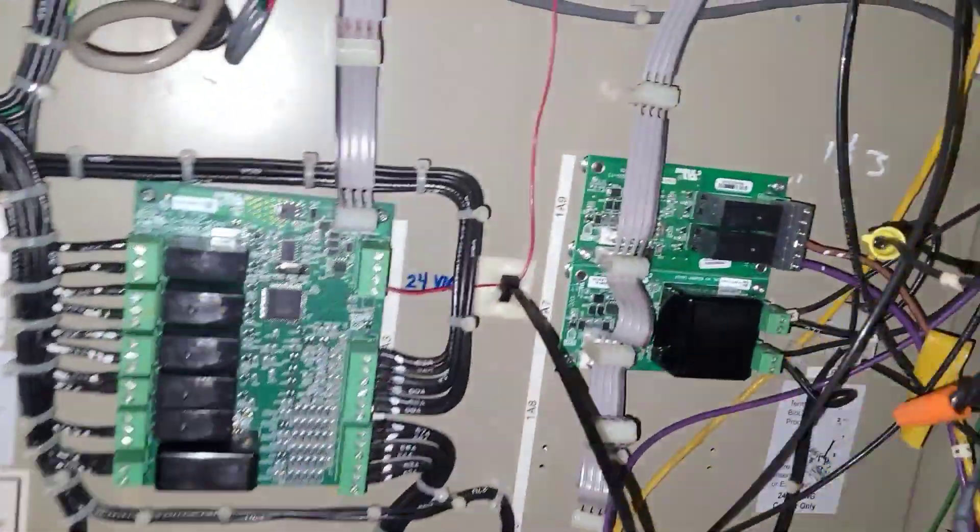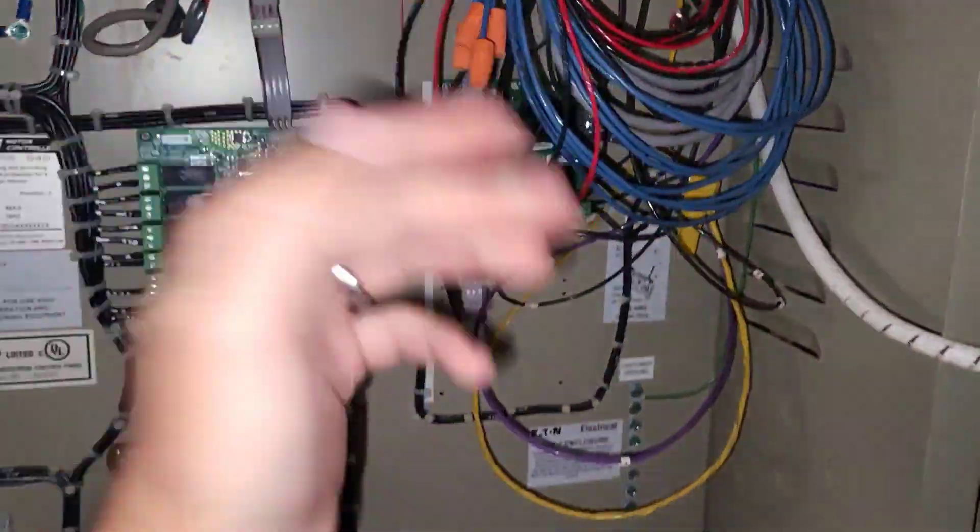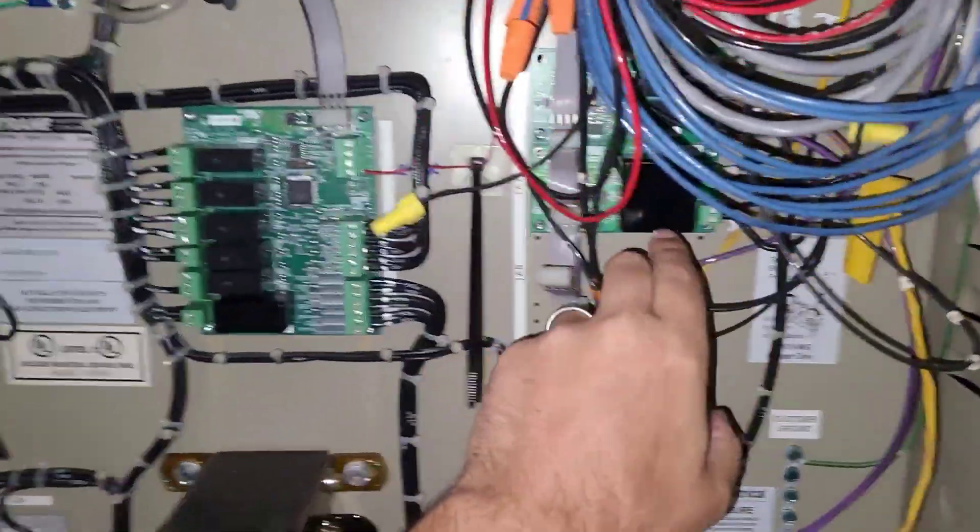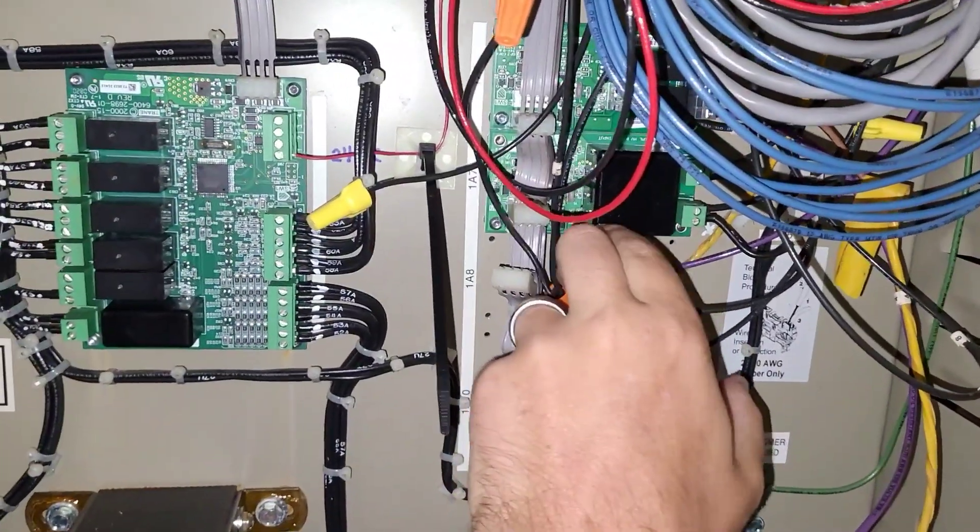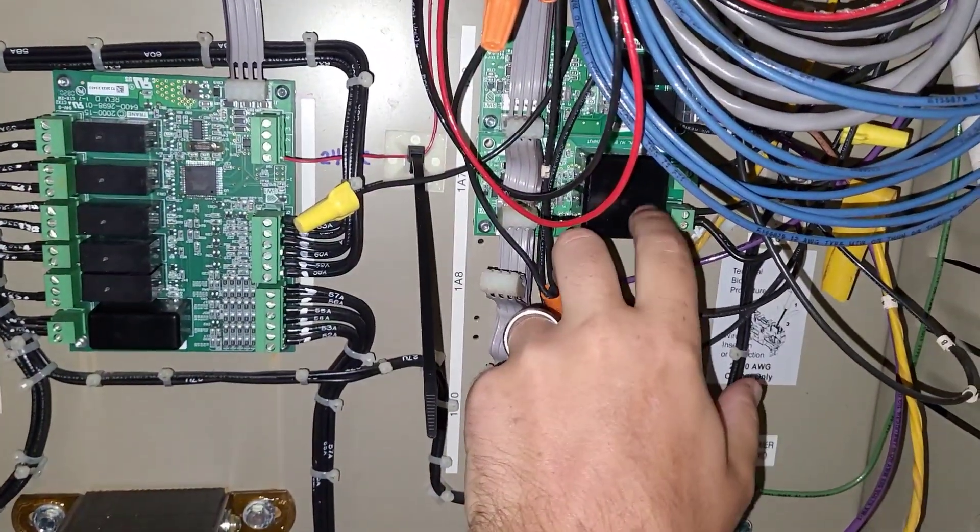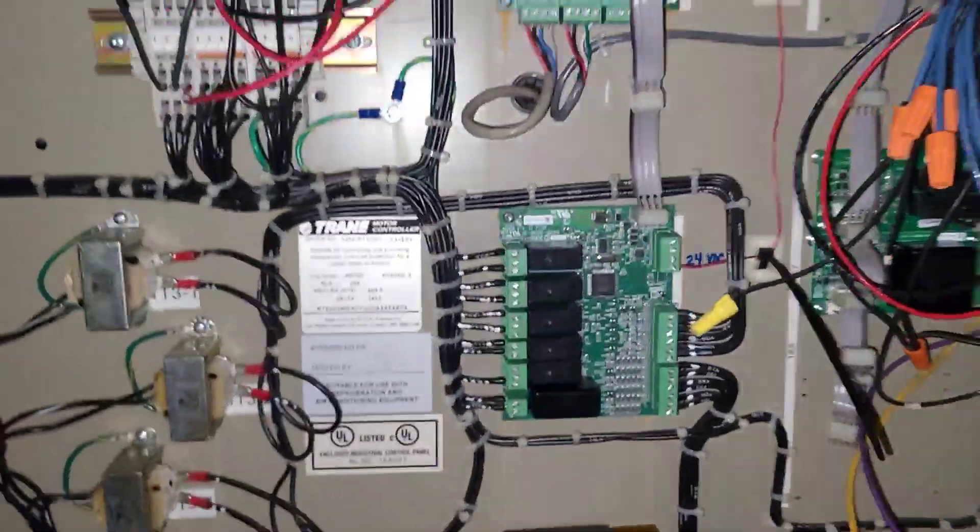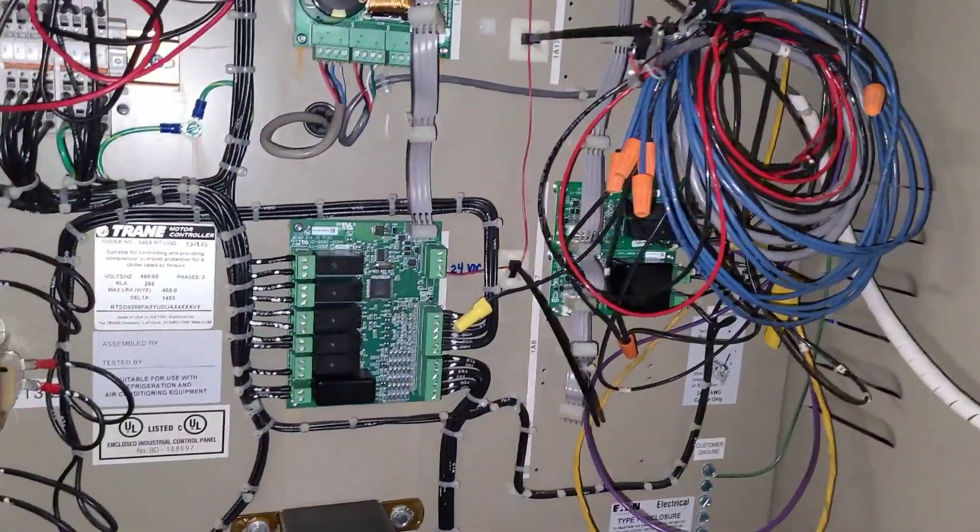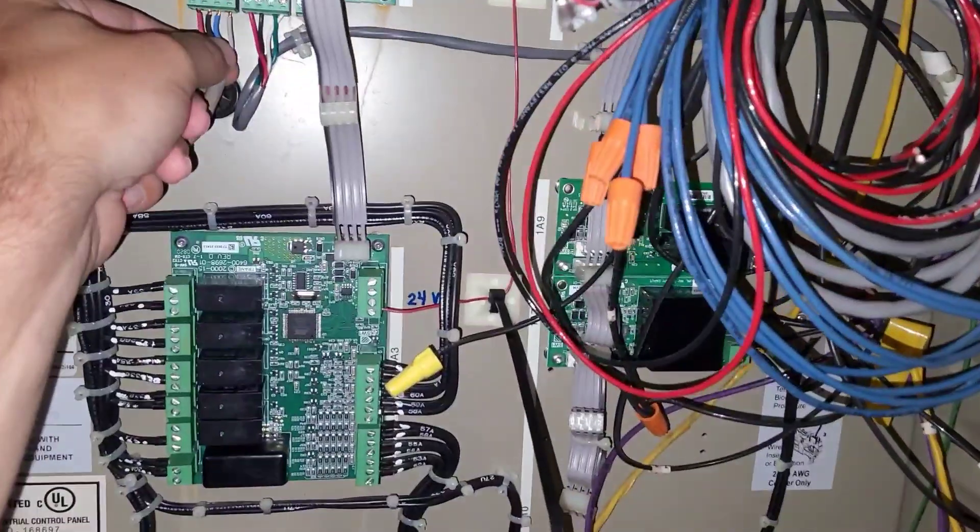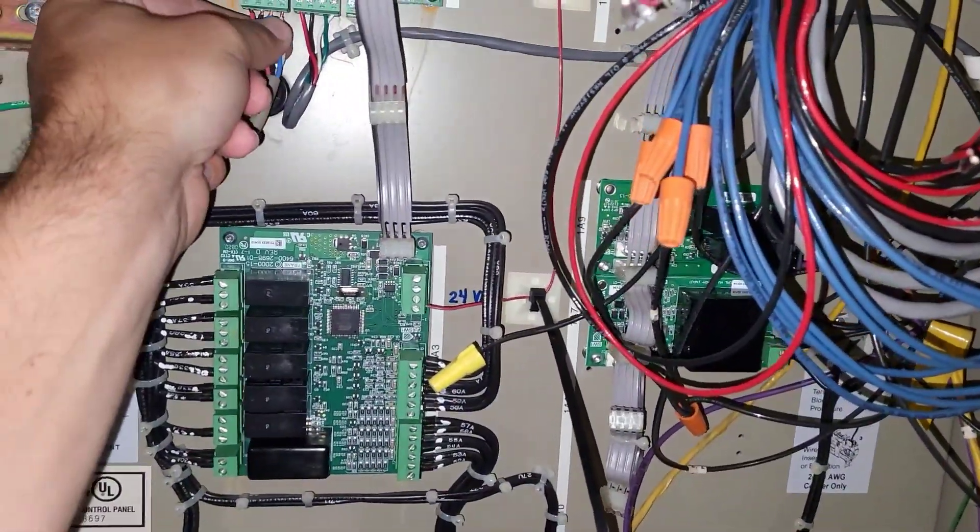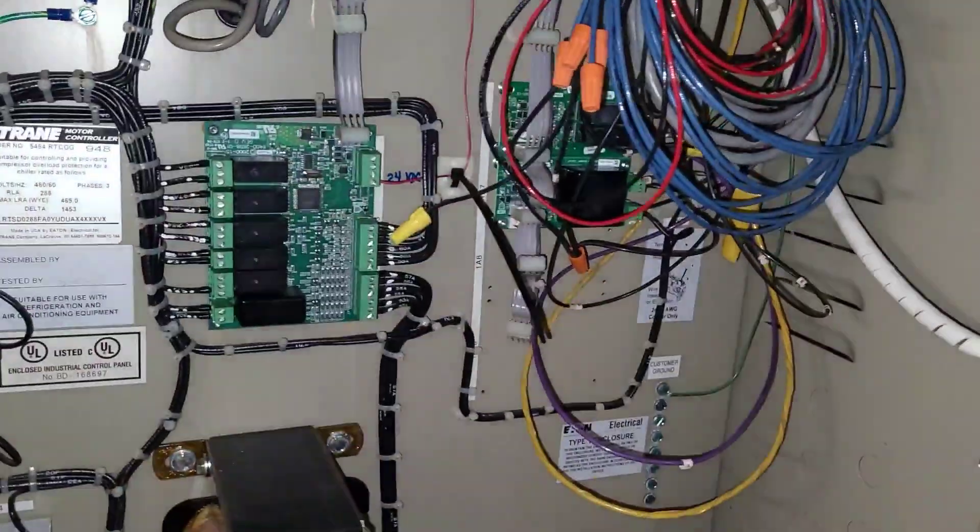It's not talking like it's supposed to. What that'll mean is the little solid state switch in here has failed. If you think about it, we did this entire panel. You're going to have occasional failures from the factory, and that's all this will be—just a legitimate failure.